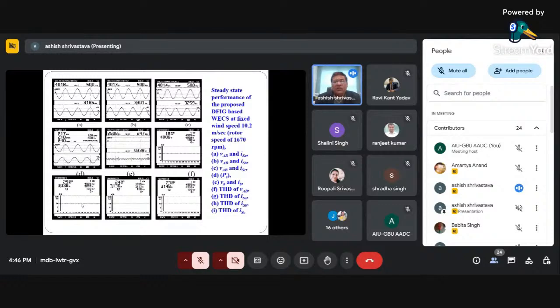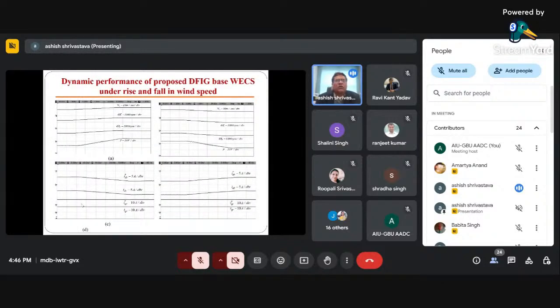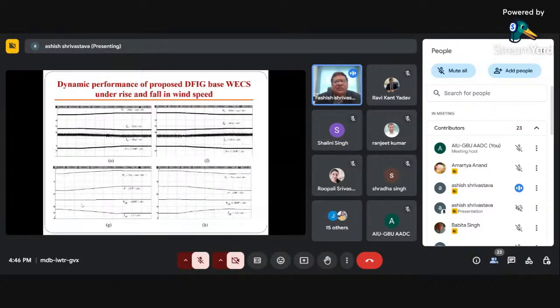Once you implement it in the hardware, this is what dynamic performance we also need to check. Suddenly you are increasing the load and suddenly you are removing the load, whether your current and the speed and your power is being stabilized or not. So this is how you need to check, and the results have been taken from the Tektronix power analyzer.